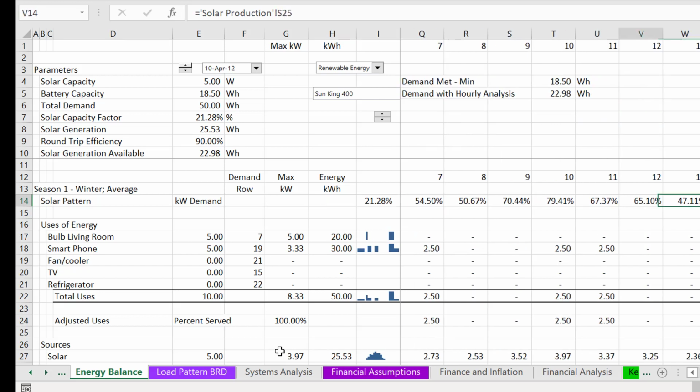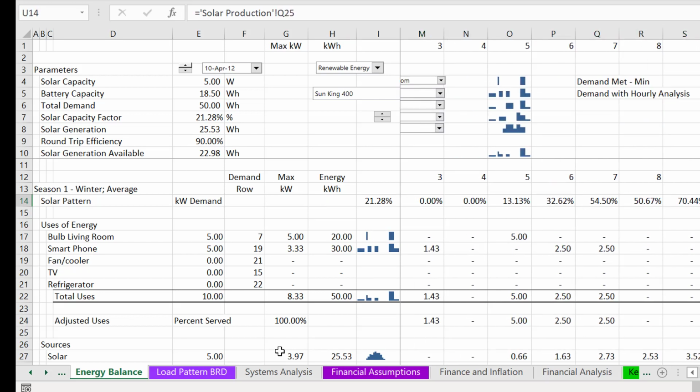So this is the percentage of the capacity, and you never ever get up to 100% capacity because the solar capacity is measured at standard testing conditions, and maybe it's not a really sunny day, or maybe it's a place where you'll never get up to this, or maybe you get it up to that level just for one day. So this is the capacity factor, the percent of the maximum capacity that we get from our solar panels in each hour.